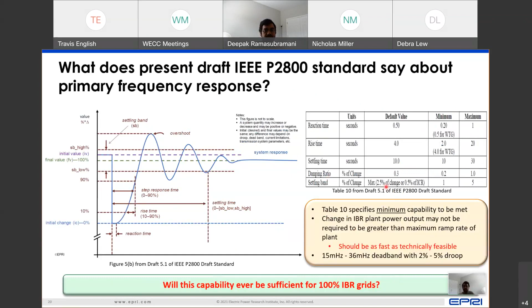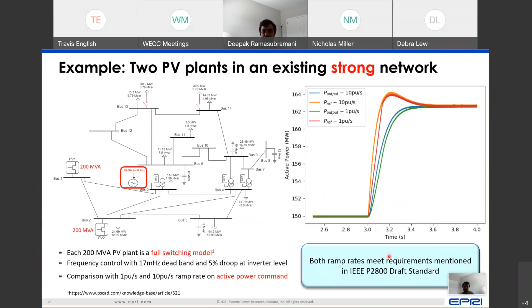And all of this we can relate back now to draft IEEE 2800 standards, wherein we talk about technically feasible capability and how fast it should be. And we can really see that if we do have these inverters respond as fast as they feasibly can, then even though in a strong system, one might see that if there is a step reduction in frequency, one might see a 200 millisecond delay in the response that's provided by these inverters, we can actually get good frequency response if you have good fast ramp rates from these inverter-based resources.